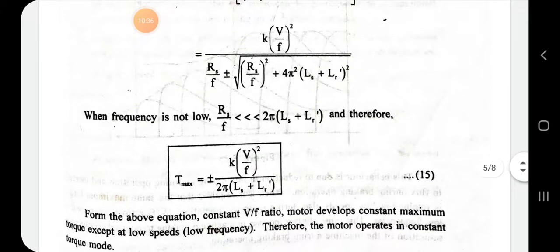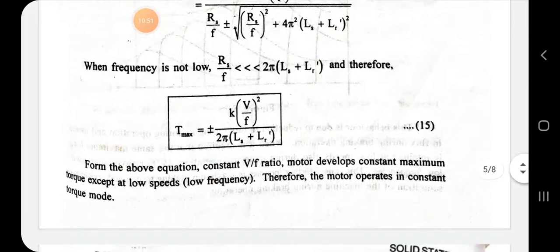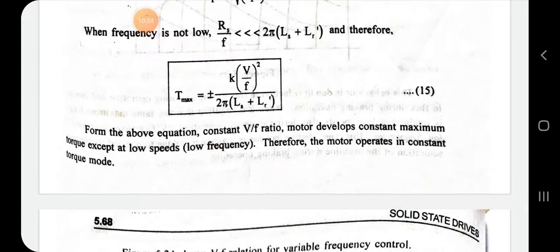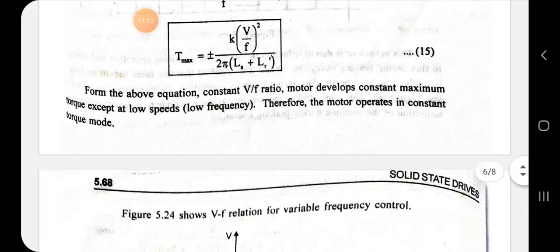When Rs/f << 2π(Ls + Lr'), the Rs term vanishes and maximum torque simplifies to: T_max = k·(V/f)² / [2π·(Ls + Lr'). For this constant V/f ratio, the motor develops a constant maximum torque. At low frequency, this method cannot achieve constant torque mode satisfactorily.